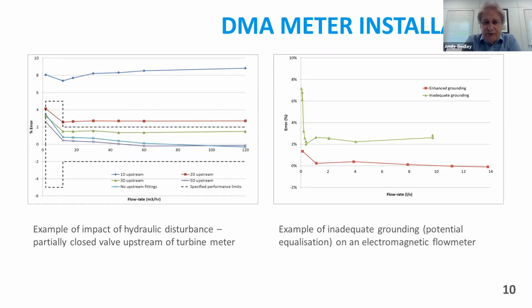So we mentioned hydraulics earlier and the importance of hydraulics. To illustrate that, the graph on the right shows test data from a particular meter with a partially closed valve upstream of a turbine meter. These were tests that we did here a while ago, and you can see quite clearly that if you put the meter very close to the partially closed valve, you get very significant errors, and as you move the meter further away from the valve, you get smaller errors.